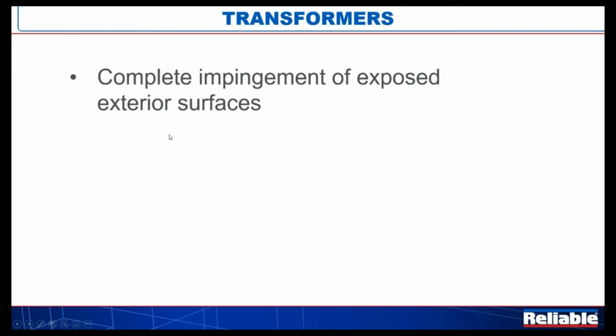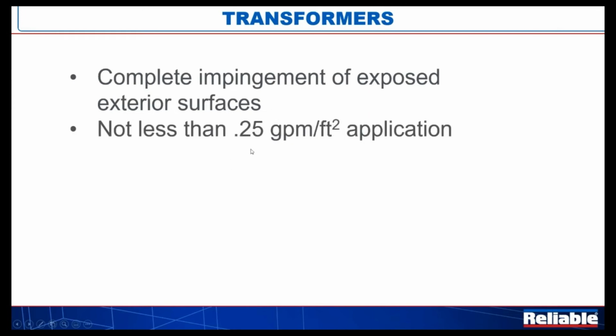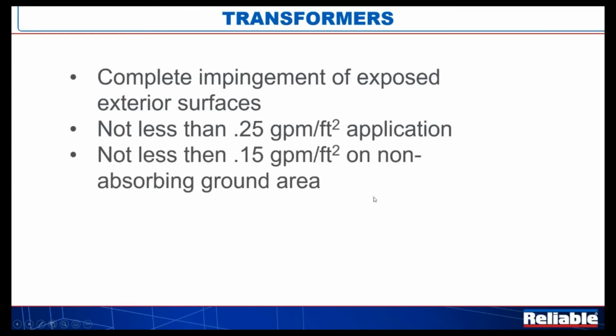Transformers, complete impingement of all exposed exterior surfaces. Okay, pretty straightforward. But if you remember that picture we looked at, there's a lot of undulations and modulations in the outside of that, so these things need to be looked at pretty carefully. No less than a 0.25 GPM per square foot application rate. These things are typically going to be sitting on concrete or on a concrete pad, so you're going to have a non-absorbing ground area beneath the transformer. You need to get nozzles down underneath there and cover that area down on the ground.